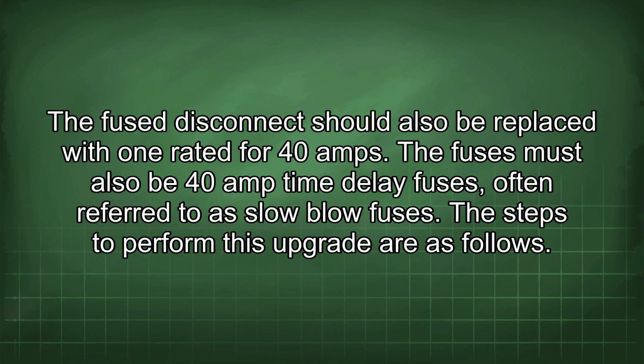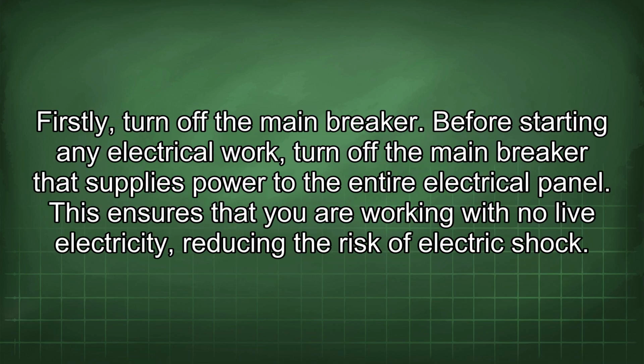The fused disconnect should also be replaced with one rated for 40 amps. The fuses must also be 40 amp time delay fuses, often referred to as slow blow fuses. The steps to perform this upgrade are as follows. Firstly, turn off the main breaker. Before starting any electrical work, turn off the main breaker that supplies power to the entire electrical panel. This ensures that you are working with no live electricity, reducing the risk of electric shock.